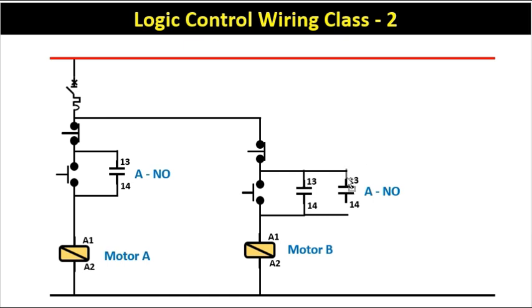I am connecting this NO contact in parallel here. This completes the circuit to start and stop motor B. You can see that if motor A gets on, then this NO contact will become NC. Due to this, power supply flows through here and goes directly to motor B, turning motor B on.